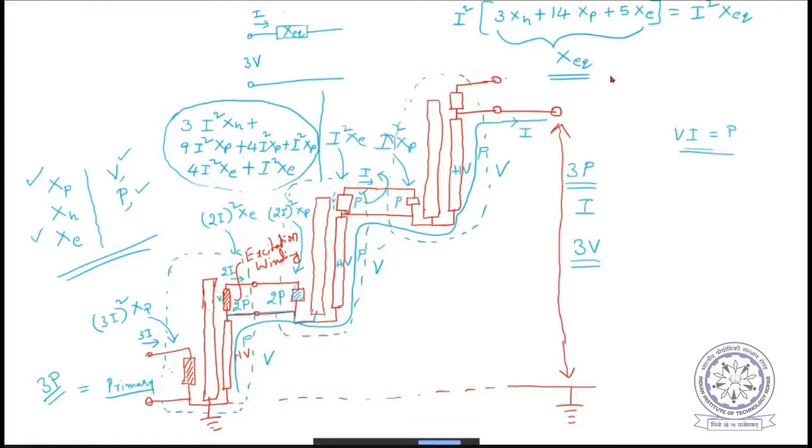When resonance occurs, huge voltage will be generated across the load, and the load under test may even break due to the excess voltage. So this problem has been identified, and this problem led to next generation transformers, called series resonant transformers.